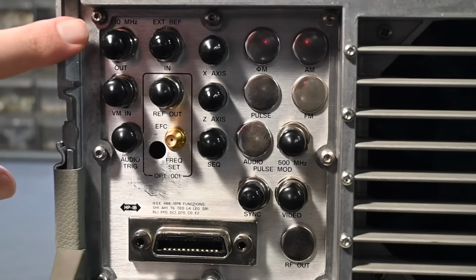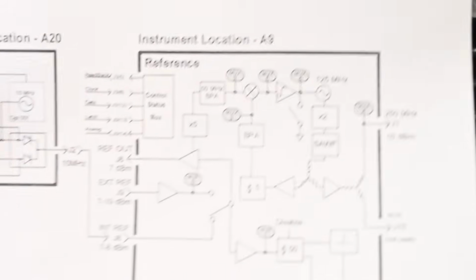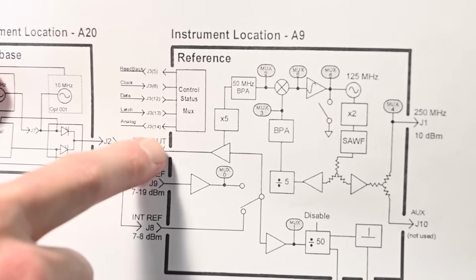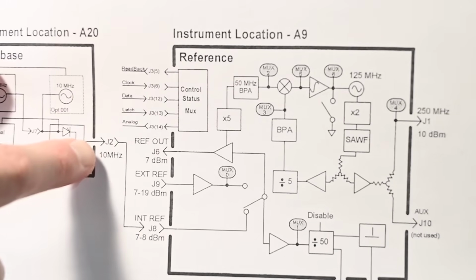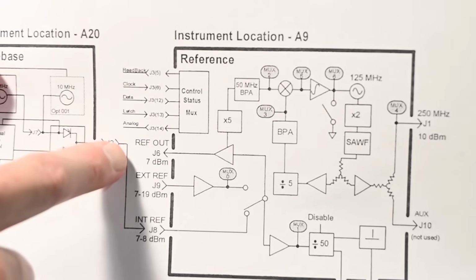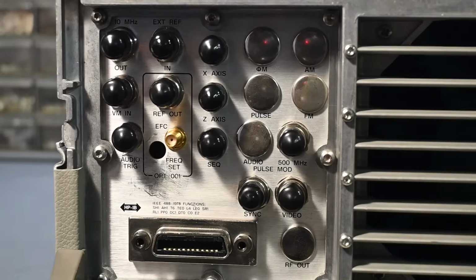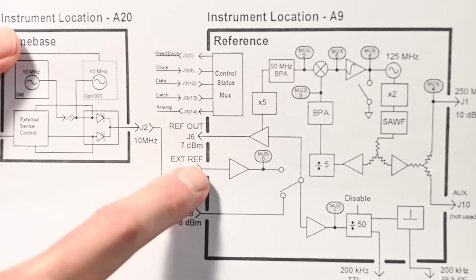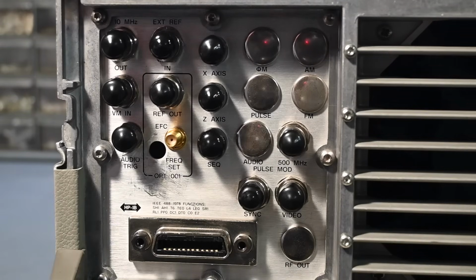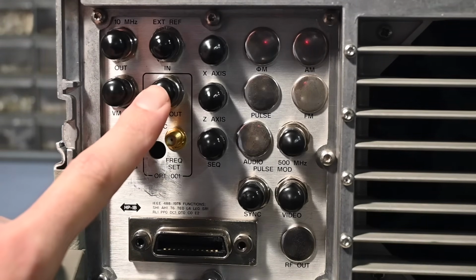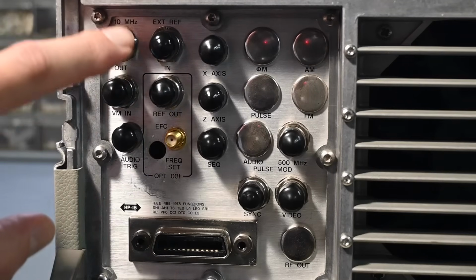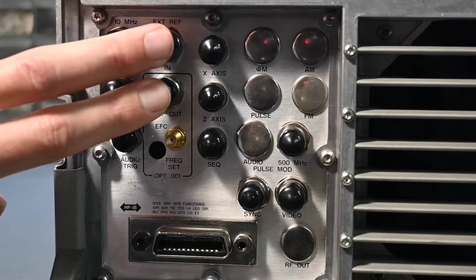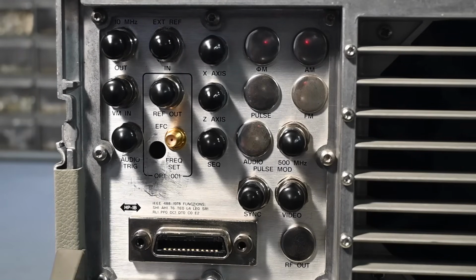And if we look right here, this says 10 megahertz out. I think what that is actually is this reference out right here, I believe. This says 10 megahertz right there. I don't think it's this connection, because I think this is an internal connection inside the instrument. There's no internal reference right here, that connection. There's nothing back here that's marked as that. And then right here, external reference in, that would be external reference going in, there. So it looks to me like this reference out for the high stability time base needs to be looped back over here to the external reference in. So I think these two need to be connected together with a coax jumper. So really a simple solution, but I overlooked that originally. I didn't realize that these two needed to be jumped together.